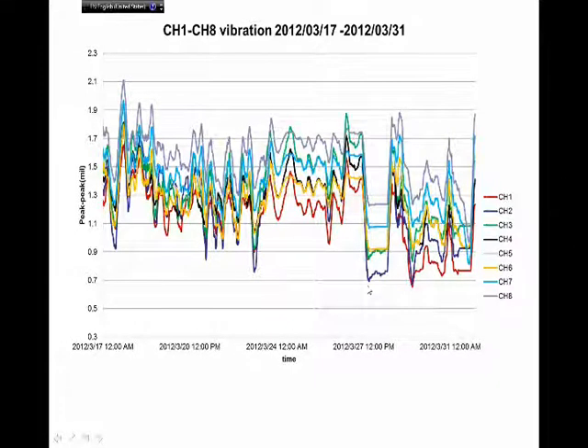So let's discuss first channel 1 to 8, and the y-axis is actually peak to peak in mil, and the x-axis is time. You can see during this time there are loading differences. The machine is going through cycles, and when the loading decreases, the amplitude also follows. Now to read the amplitude, the highest is channel 7 and channel 8. You see, this is the grayish purple color, followed by the blue.